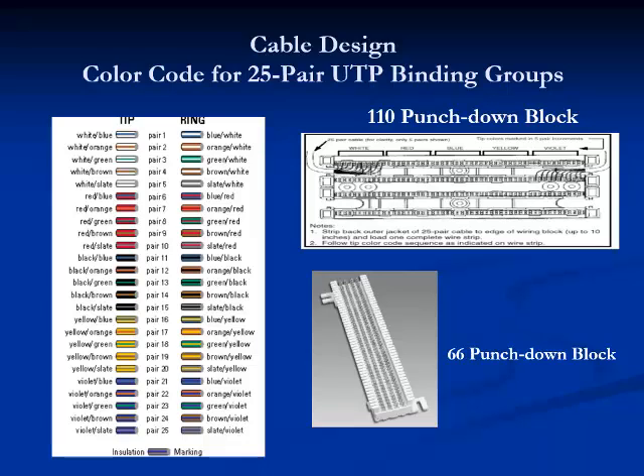The binding colors white, red, black, yellow, and violet identify each 5 pair within the 25 pair of wire. The blue, orange, green, brown, and slate identify each wire pair within the 5 pair. The tip simply means the plus leg of the telephone circuit, and the ring is the minus or the ground. Each wire pair can be one telephone number.